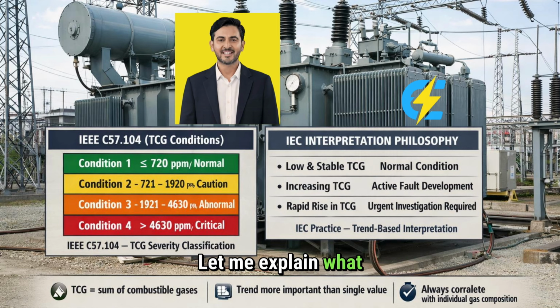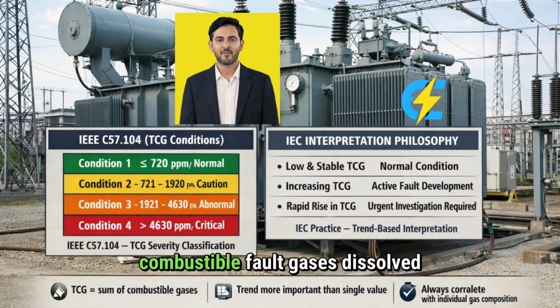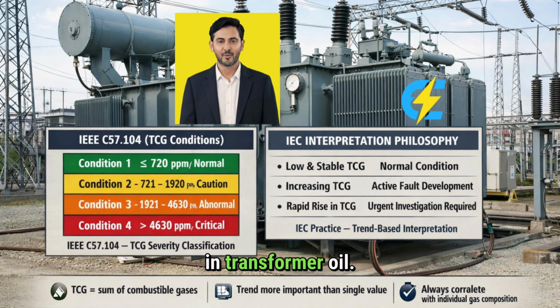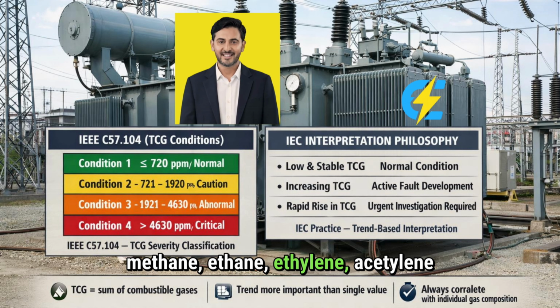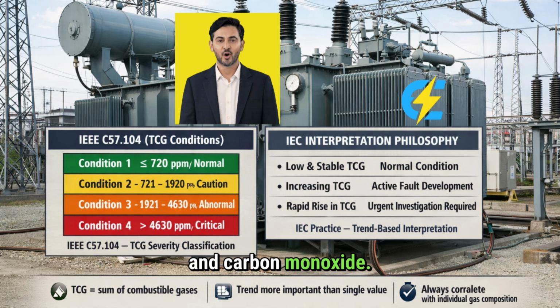Let me explain what TCG really means. Total combustible gases is the sum of all combustible fault gases dissolved in transformer oil. According to IEEE C57.104, TCG typically includes hydrogen, methane, ethane, ethylene, acetylene, and carbon monoxide. Notice that carbon dioxide is not included because it's not combustible. This is a critical distinction that many engineers miss in the field.